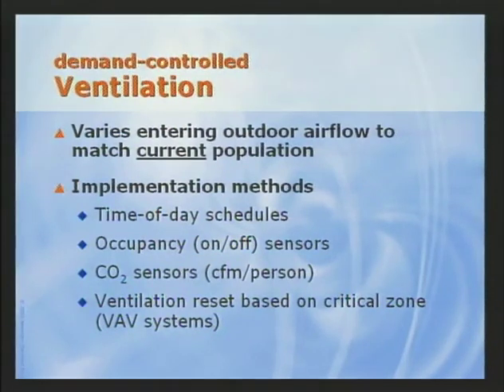Ventilation reset on variable air volume systems monitors the airflow provided to each zone and resets the outdoor air quantity at the air handler to assure the zone requiring the highest concentration of outdoor air is always satisfied. Regardless of which strategy is employed, a means of modulating and in some cases measuring outdoor air will be required on the air handler or terminal unit. Engineers' newsletters have been written that specifically address each of these control strategies and will be listed in the bibliography.